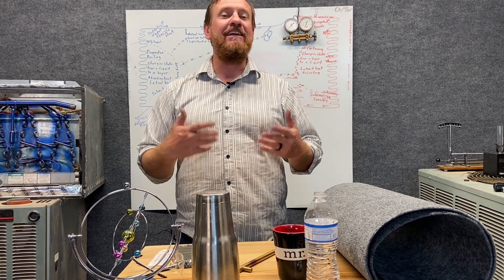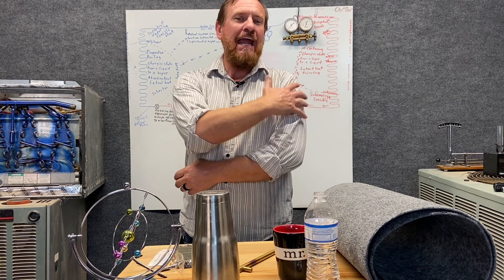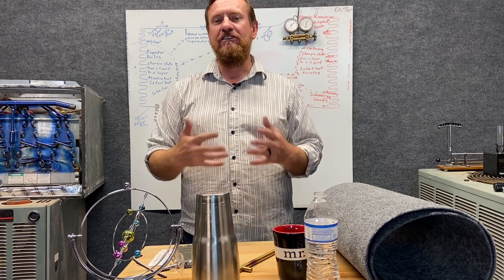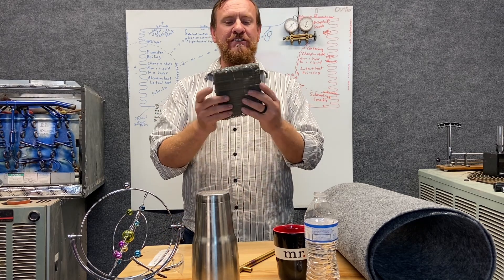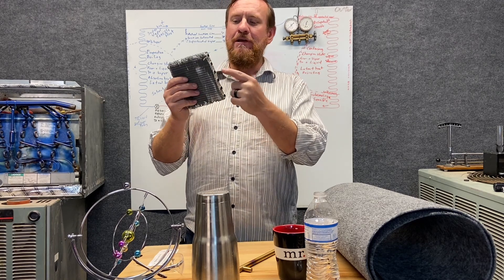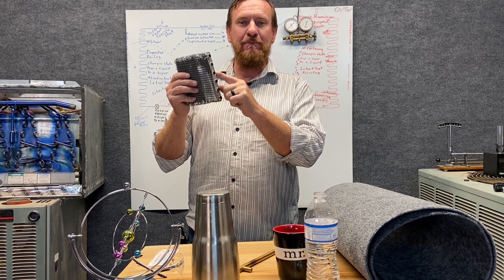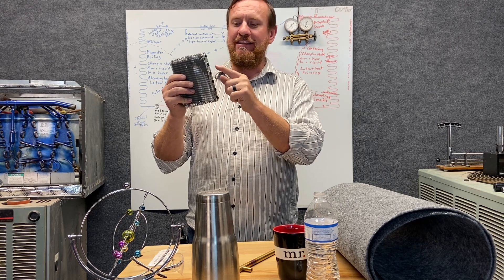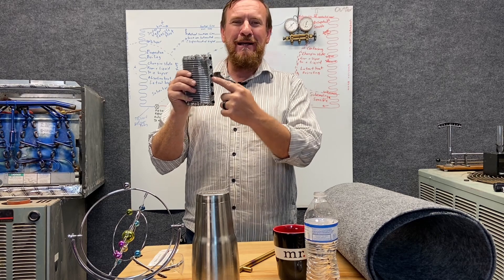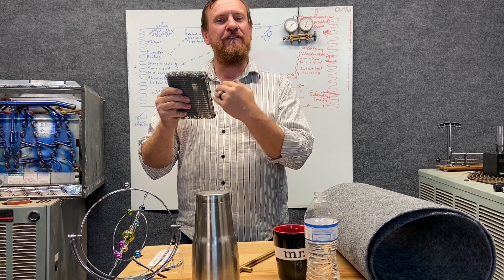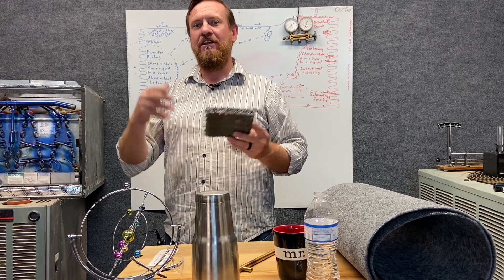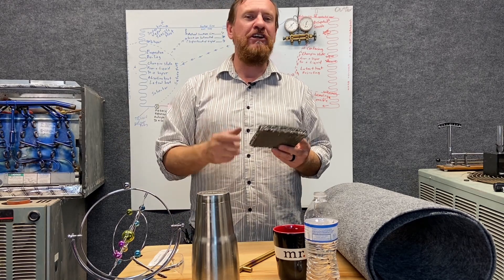When you touch doors or anything, that's conduction. The air around you — you're conducting heat from your body to the air. On the refrigeration side, we're transferring heat by conduction because heat is conducting from the air touching the aluminum fins, then conducting from the aluminum to the copper pipes in the middle, and from the copper pipes to the refrigerant. All of that is conduction via direct contact. That is conduction — direct contact, molecule touching molecule.